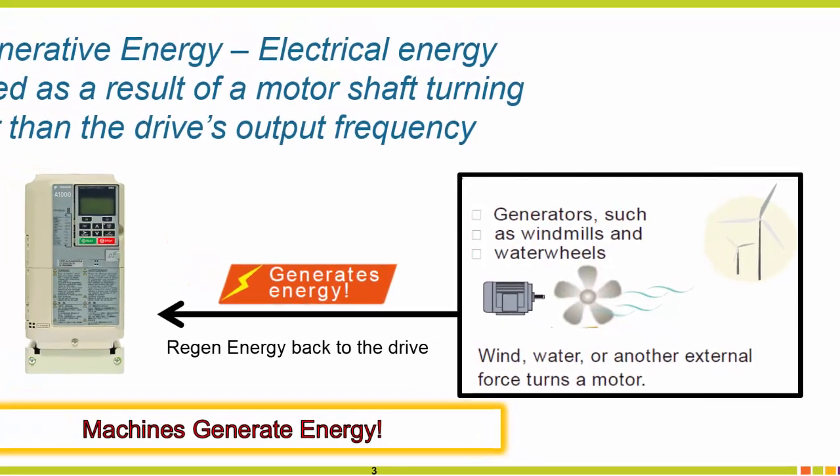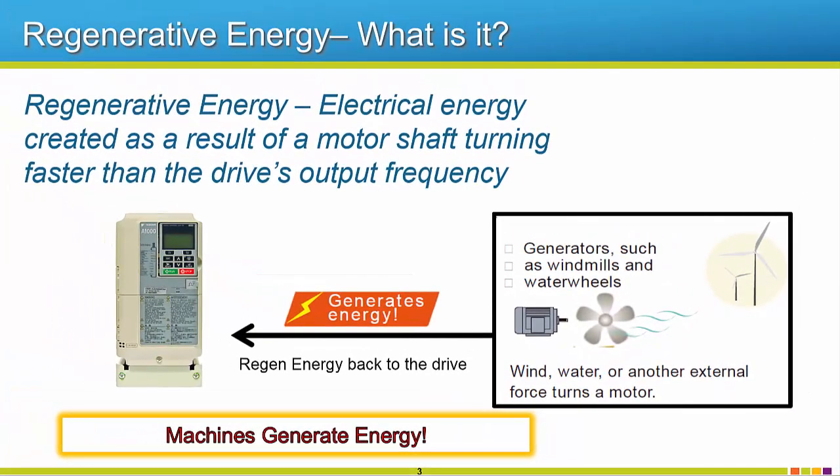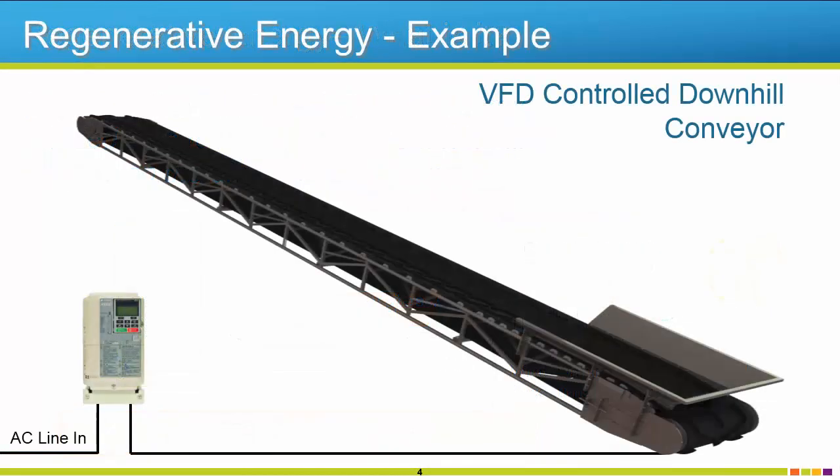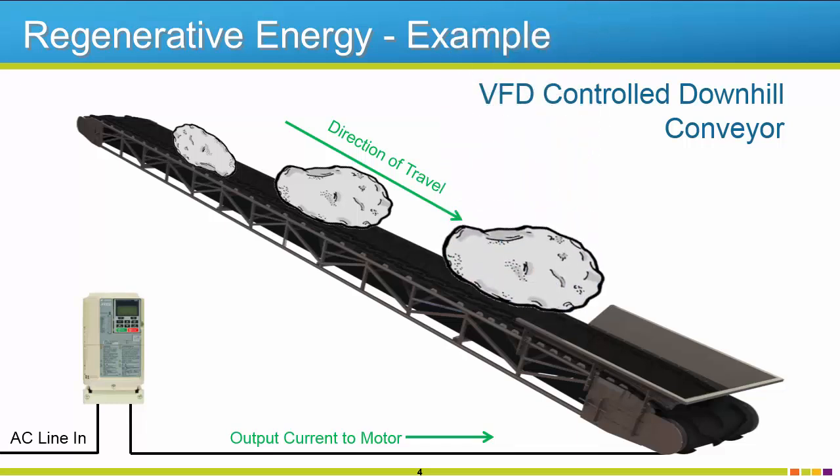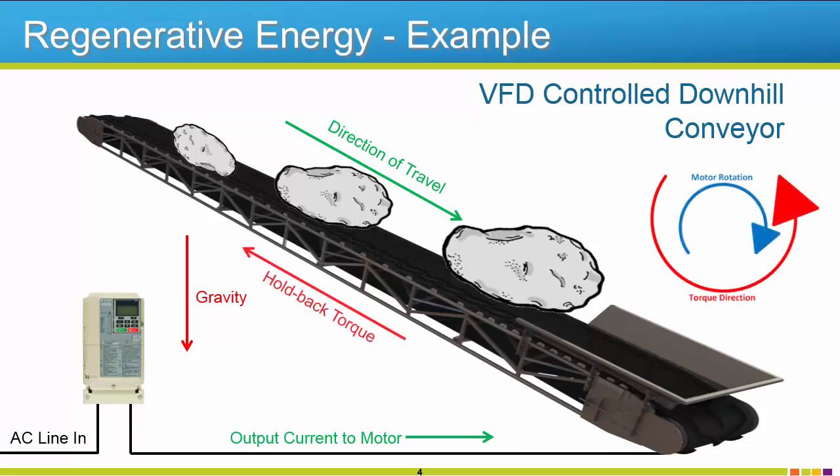Now you may be thinking, hey, my application generates energy? Great, so what happens to that energy? Where does it go? To answer that question, let's look at one more application example and discuss how regenerative energy can be a double-edged sword. Pretend we have a downhill conveyor with the drive running the motor on that conveyor. In this application, there is a lot of regenerative energy due to gravity on the product. The drive will command the motor to run at a certain speed and direction. This is the speed reference. Because of the weight of the product on the conveyor and the force of gravity, the conveyor will naturally want to accelerate downhill without the need for the drive to perform any work. When the conveyor starts to run faster due to gravity and the load, the motor must hold the load back to maintain the commanded speed reference. This is called hold back torque.